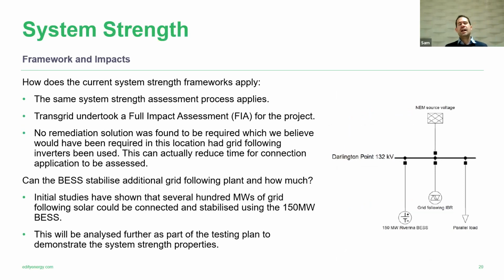Moving to how this fits into the existing system strength framework: the same framework applied to any generator connecting applies here. We undertook a preliminary impact assessment, and these were considered inverter-based resources, which triggered a full impact assessment for our project. The project went through that assessment and found no remediation solution was required. In fact, it found the project was benefiting the network, improving some existing issues, so we were able to pass through that process quite quickly.